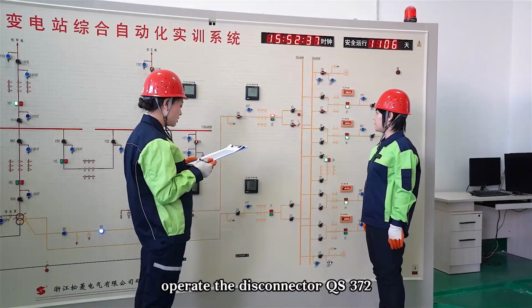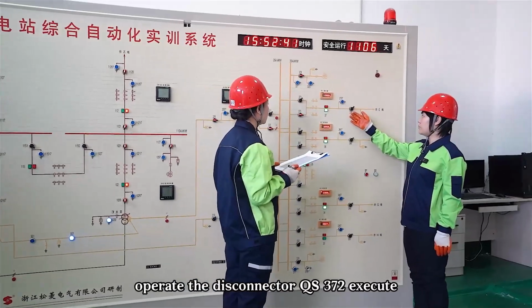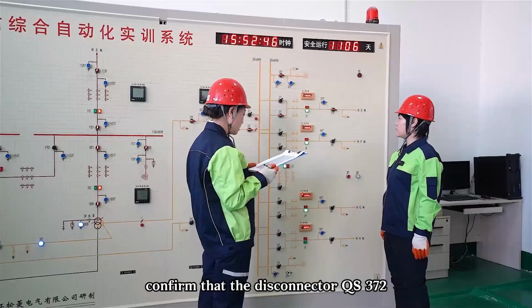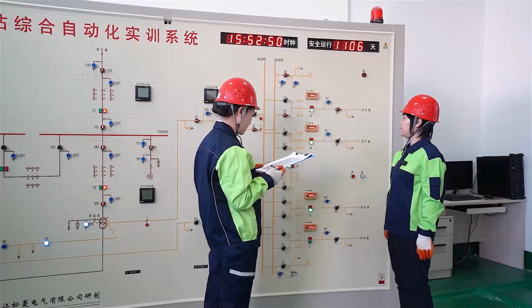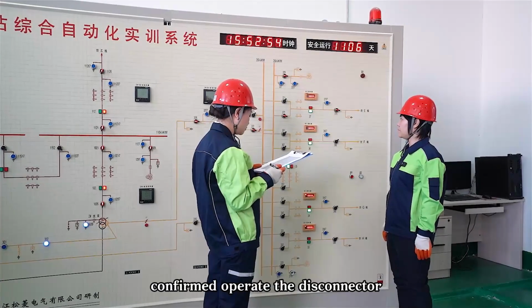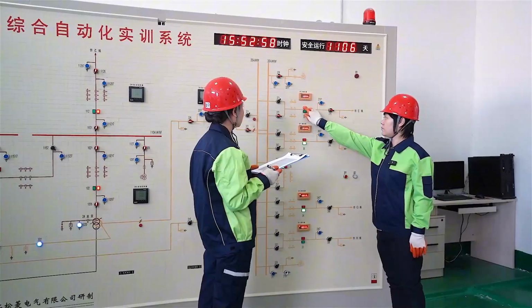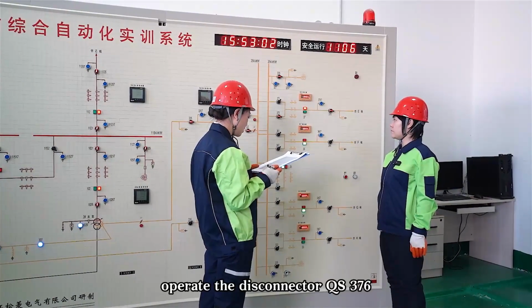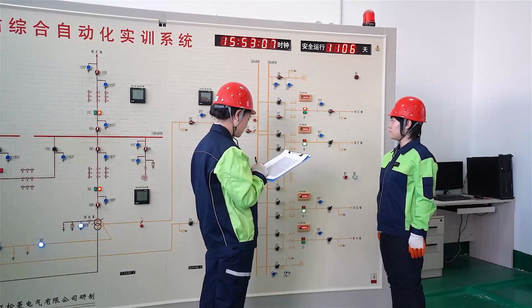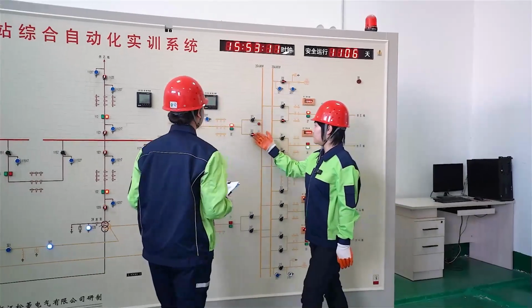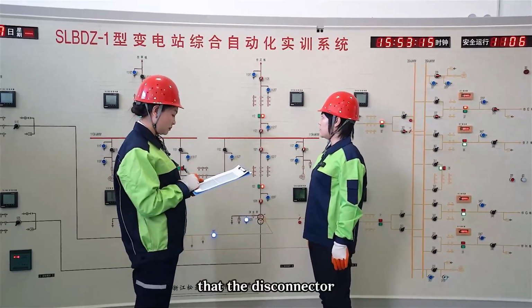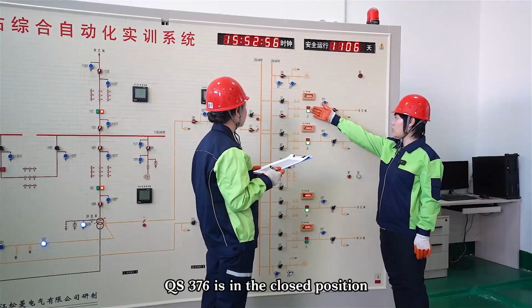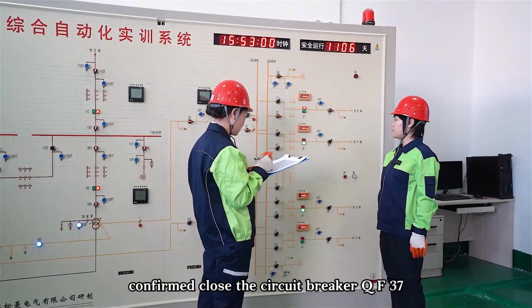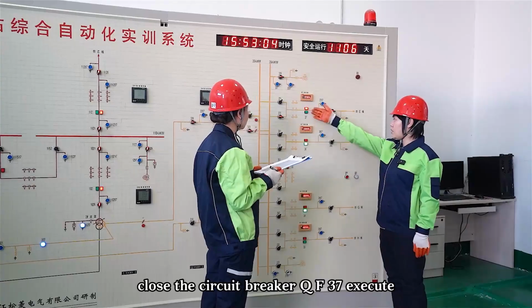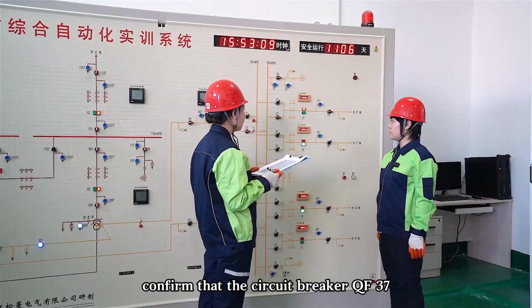Operate the disconnector QS372. Execute. Confirm that the disconnector QS372 is in the closed position. Confirmed. Operate the disconnector QS376. Execute. Confirm that the disconnector QS376 is in the closed position. Confirmed. Close the circuit breaker QF37. Execute. Confirm that the circuit breaker QF37 is in the closed position. Confirm. Operation completed. Reporting completed.